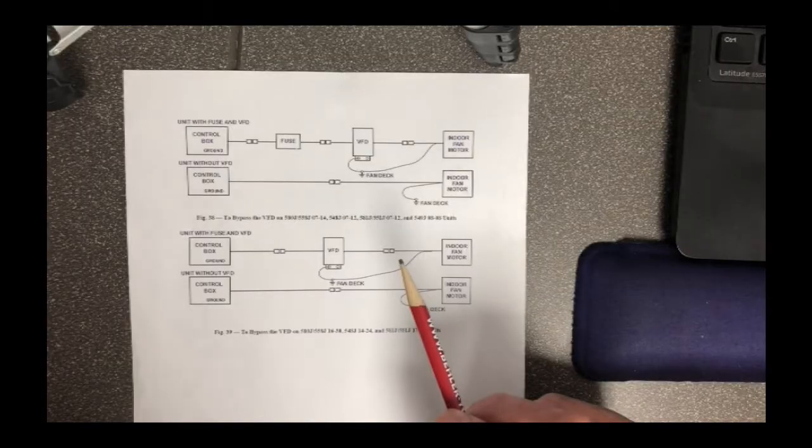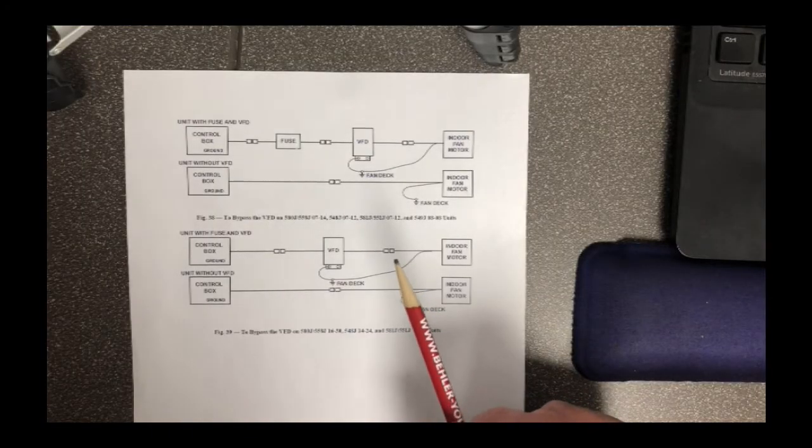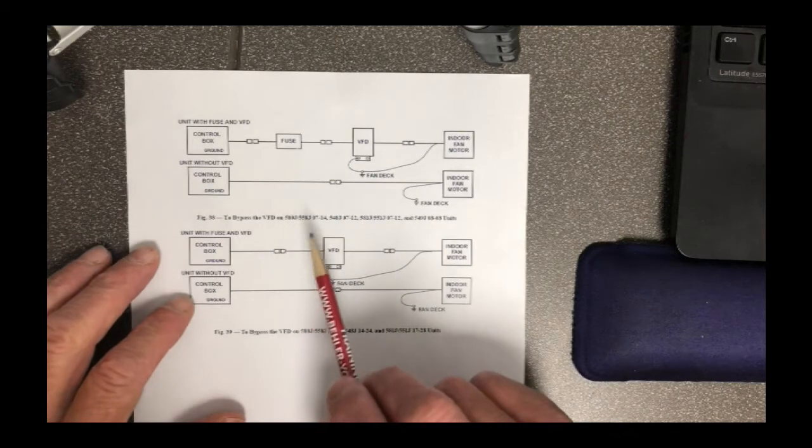To do this, definitely shut the power off to the unit first. And secondly, once you power it back up, that blower is going to run full speed, full time, with no control, but the unit will work until you get back to the drive.